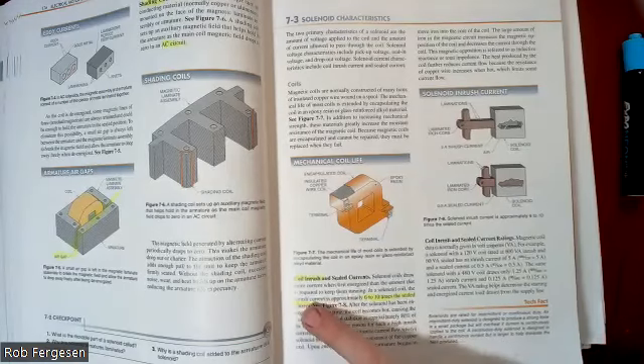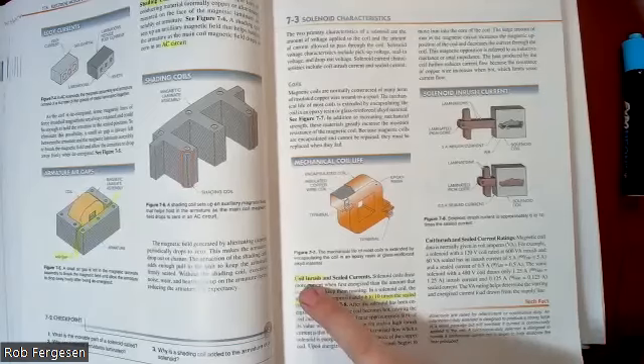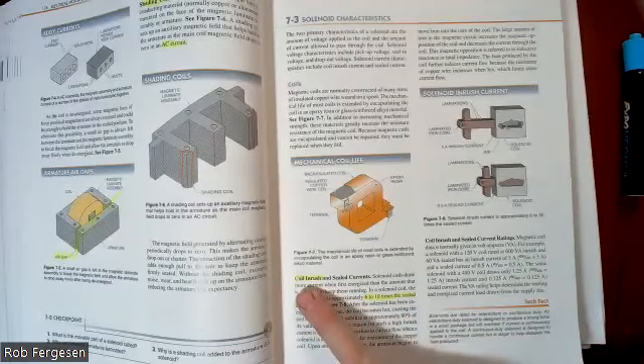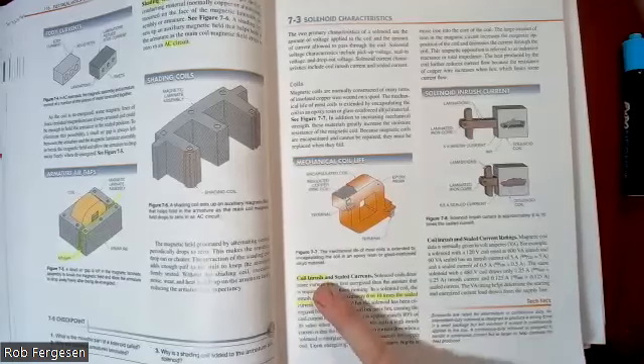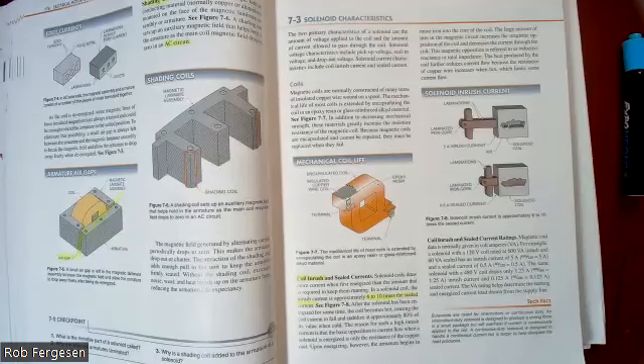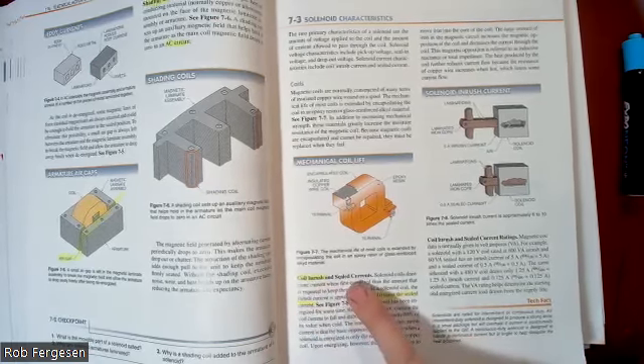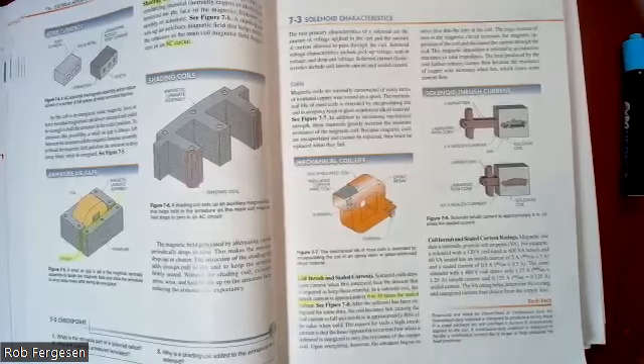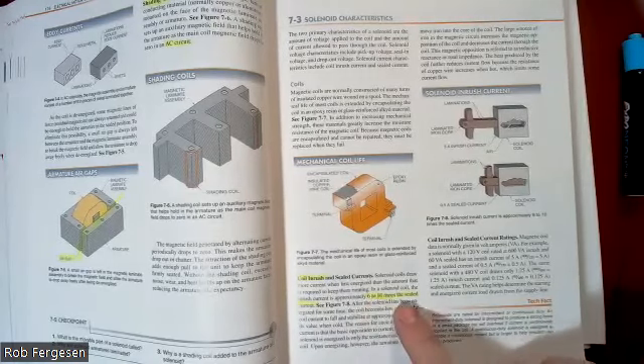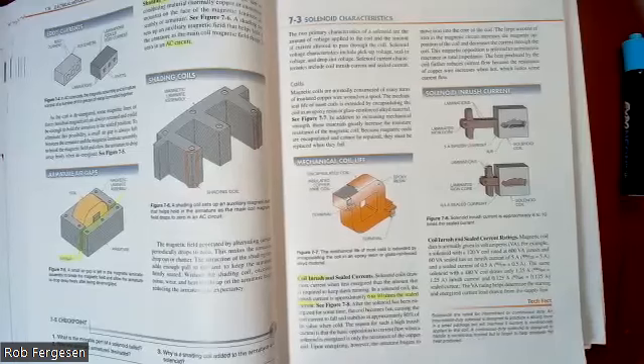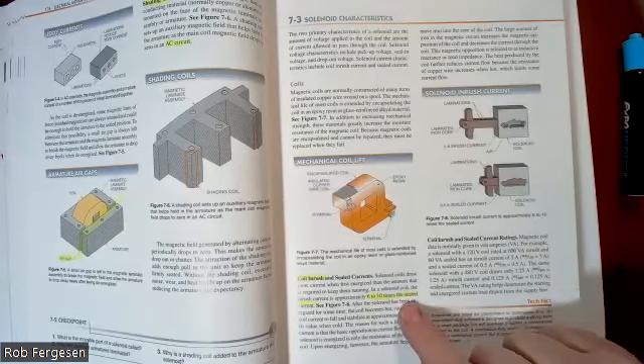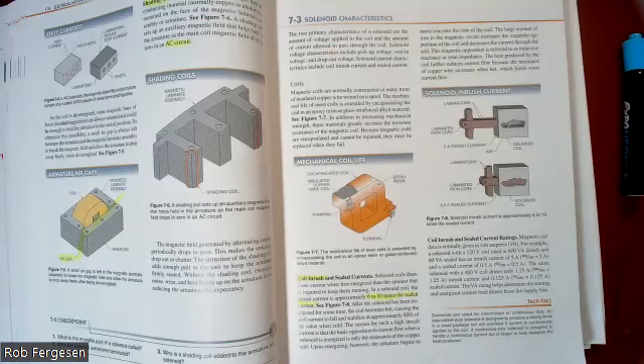Another key fact about coils, and any kind of energizing of a coil, just like energizing a motor, is something called inrush. When you first turn it on, you get a whole bunch of extra current. So anytime you fire up a coil, you get extra current. When you have it on already, the sealing current is usually much lower. The interesting thing to me is it's 6 to 10 times your current to turn it on than it is to keep it sealed. That little burst of energy, and this is where I'm going to divert from the book.